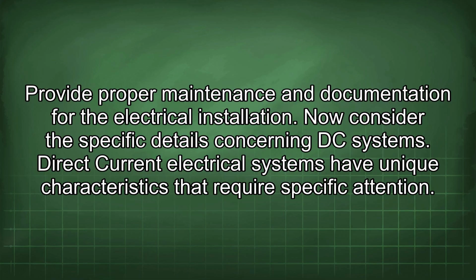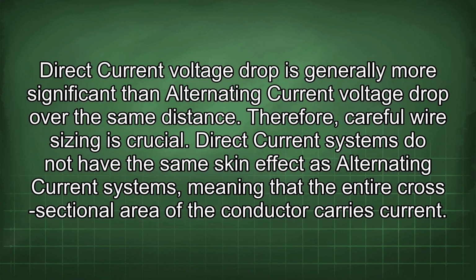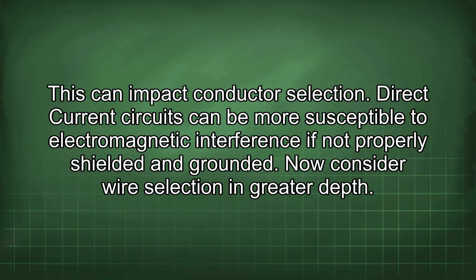Now consider the specific details concerning DC systems. Direct current electrical systems have unique characteristics that require specific attention. Direct current voltage drop is generally more significant than alternating current voltage drop over the same distance. Therefore, careful wire sizing is crucial. Direct current systems do not have the same skin effect as alternating current systems, meaning that the entire cross-sectional area of the conductor carries current. This can impact conductor selection. Direct current circuits can be more susceptible to electromagnetic interference if not properly shielded and grounded.